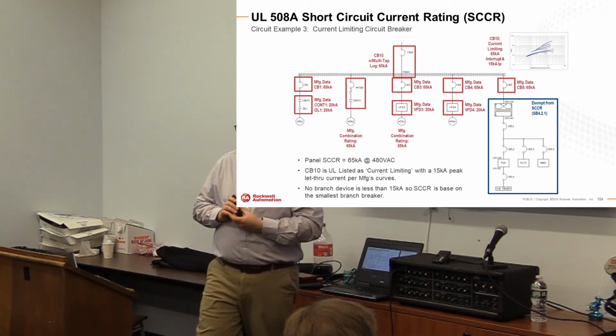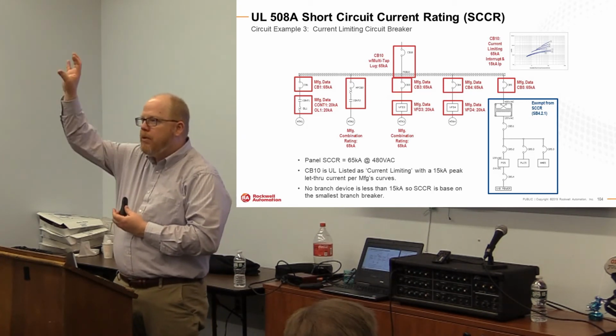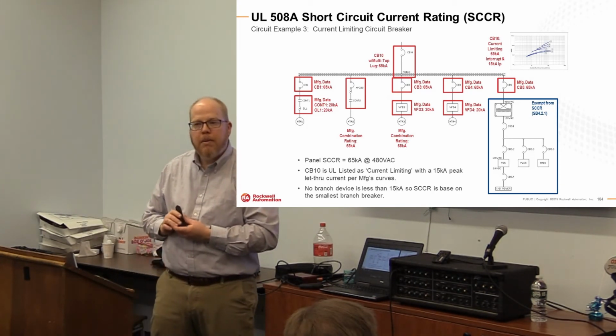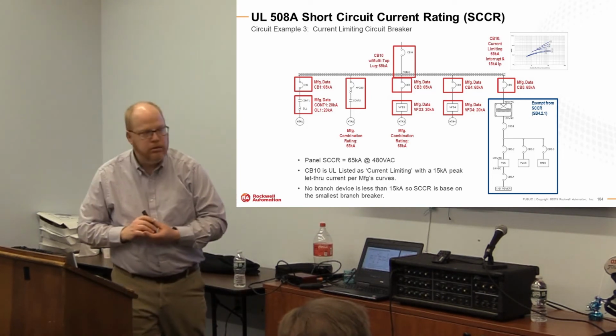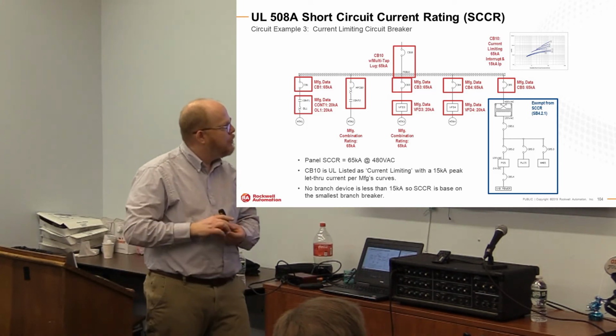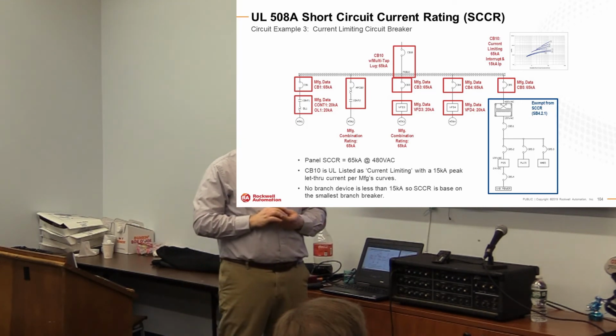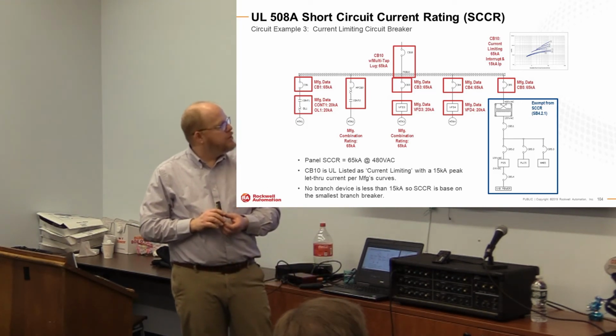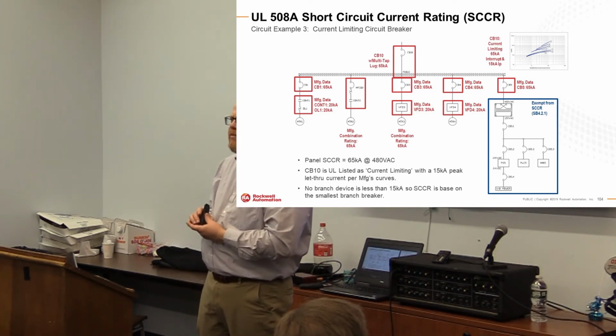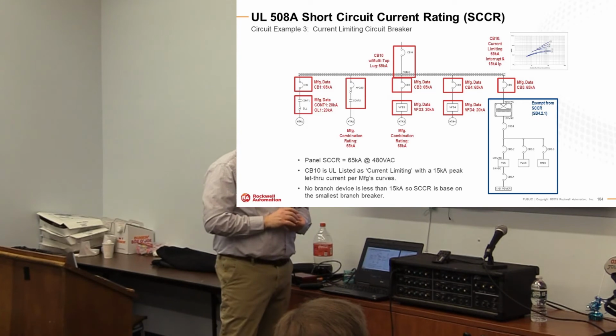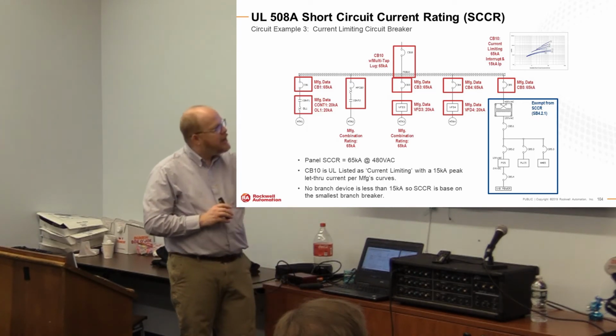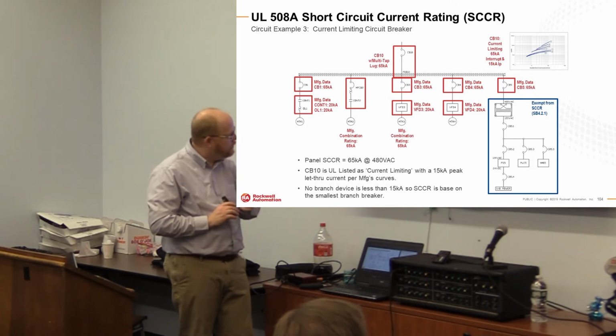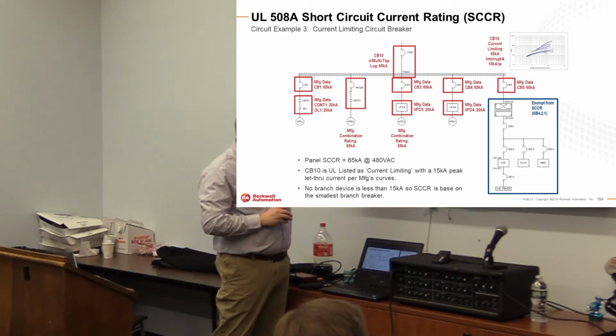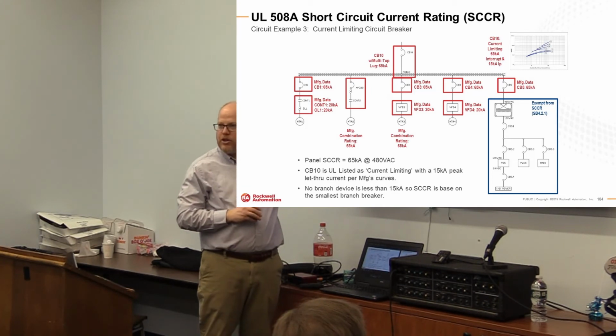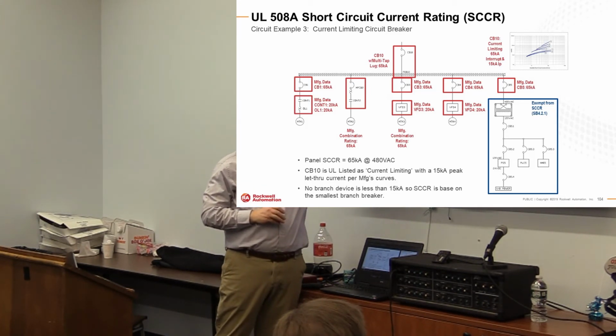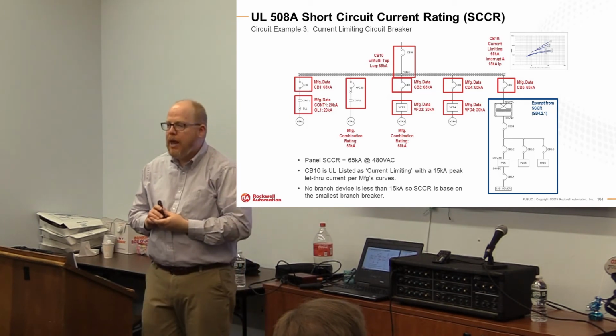Let me show you an example of current limiting with a circuit breaker. Again, up in the right-hand corner, I show that you would have to grab the manufacturer trip curve data, right? And you would have to read that chart and come up with two pieces of data. One of them is the interrupt rating of the device, and one of them is the peak let-through current of that device. In this case, it's 65 kA and 15 kA. That needs to be known because that is what the downstream components are subjected to. So the evaluation skips over the branch and looks at all the components downstream, and is it as good or better than 15 kA?